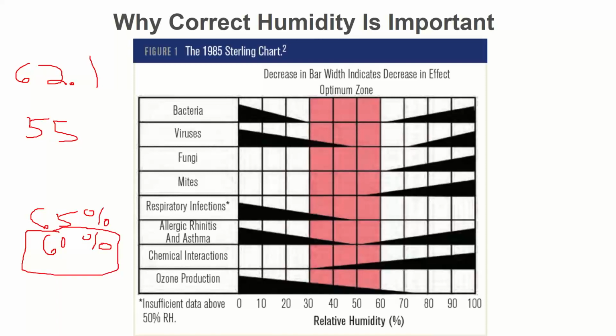I'll just tell everybody: your maximum indoor humidity should never be above 60%. If it is, bad stuff's happening. Most of the buildings I go to, and by most I mean more than 90-some% of them, have days where it's more than 60% humidity in the space, and that's a problem.